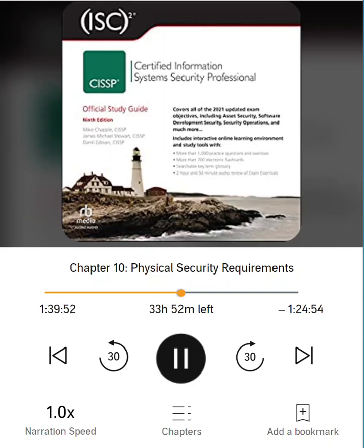Halon is an effective fire suppression compound. It starves a fire of oxygen by disrupting the chemical reaction of combustion, but it degrades into toxic gases at 900 degrees Fahrenheit. Also, it is not environmentally friendly. It is an ozone-depleting substance. The 1989 Montreal Protocol initiated the termination of manufacturing of ozone-depleting substances, which includes halon.